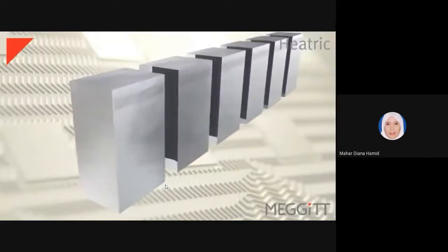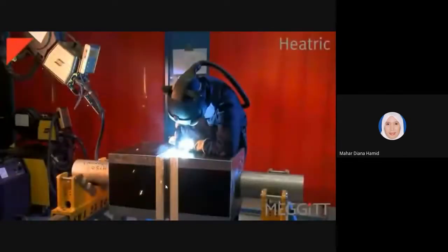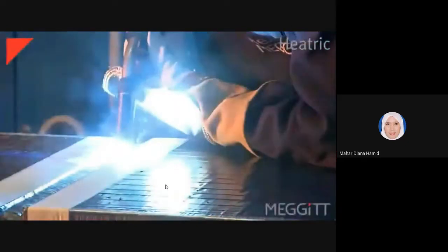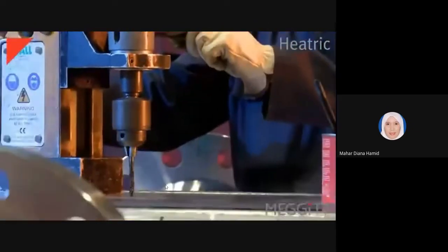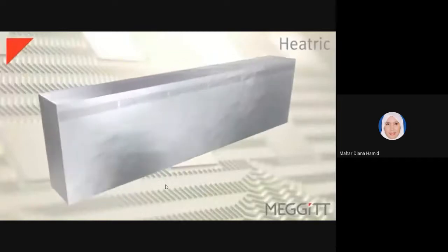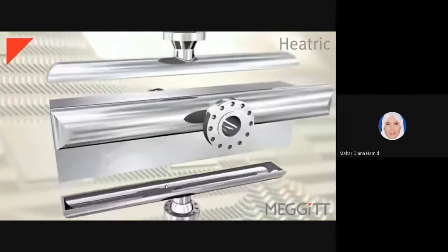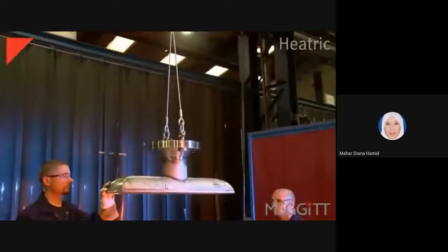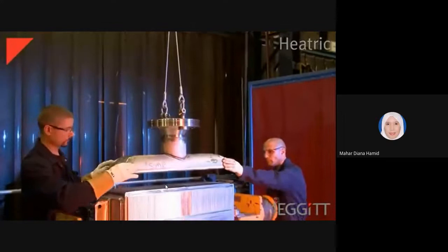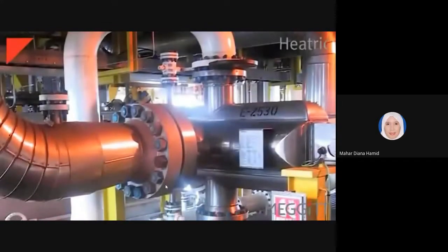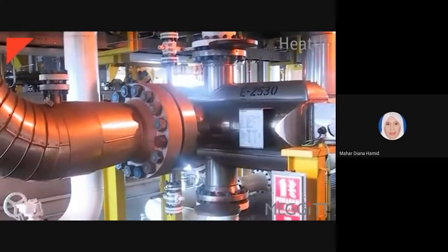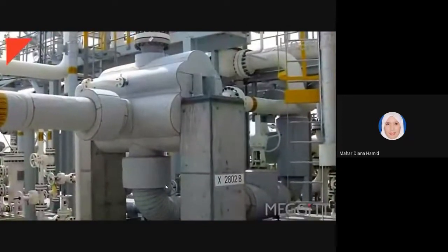In order to achieve the performance, a number of blocks may be required. These individual blocks are then welded together to form an exchanger core of the required capacity. In order to confirm the absence of pressure between each block, an interblock vent is created in the block-to-block weld. Once the core is complete, headers, including prefabricated nozzles, are attached. These are half cylinders which distribute fluids into the exchanger core. The exchanger is connected to the customer's process piping by way of nozzles. The nozzles can be designed to meet the customer's individual requirements and typically use flanges, compact hubs, or weld preparations.